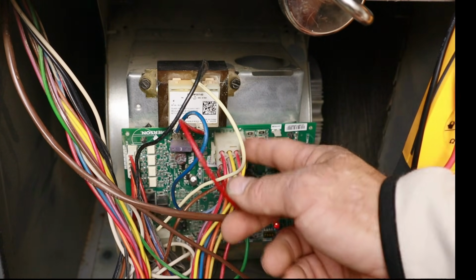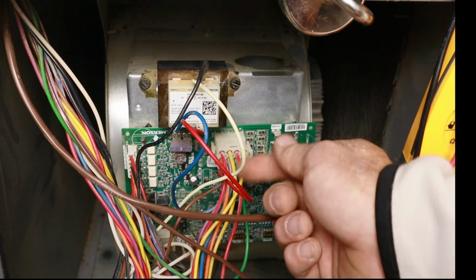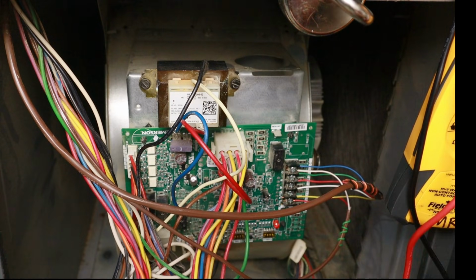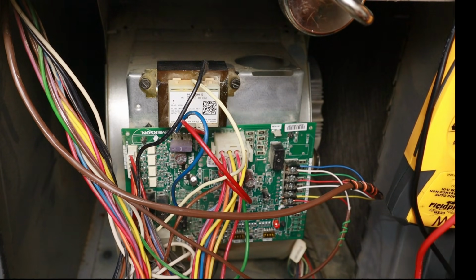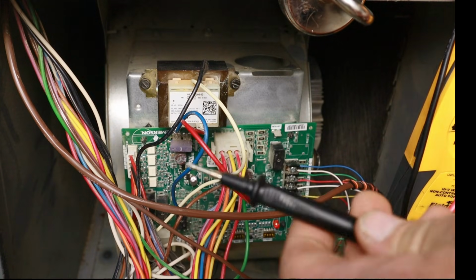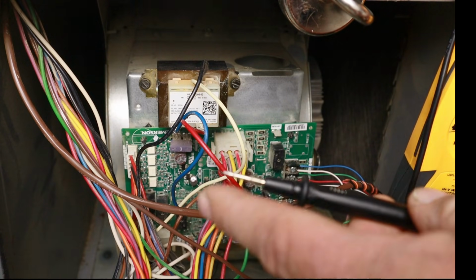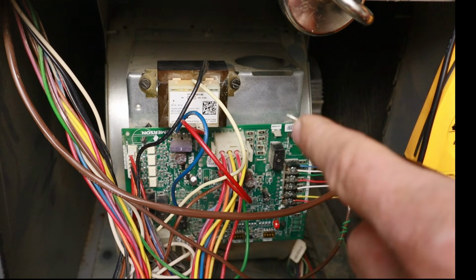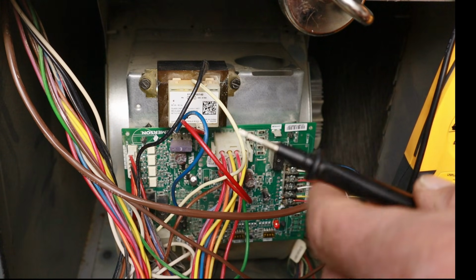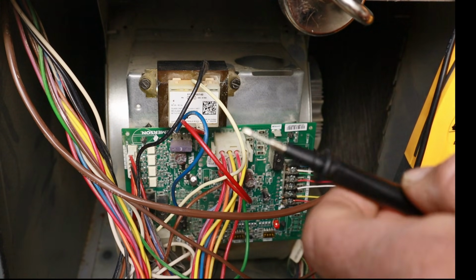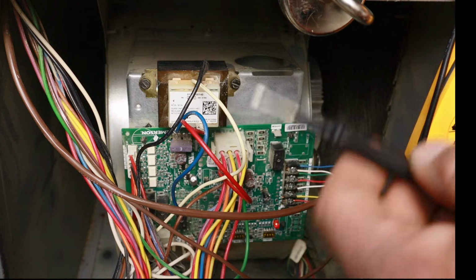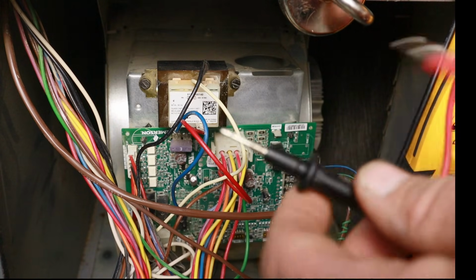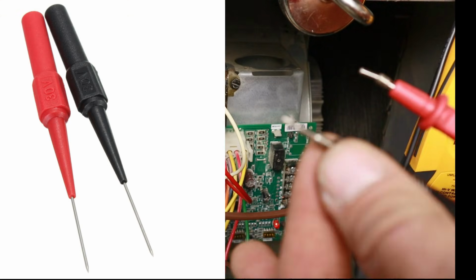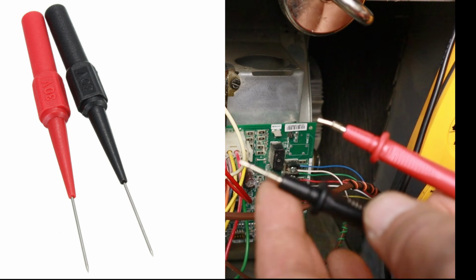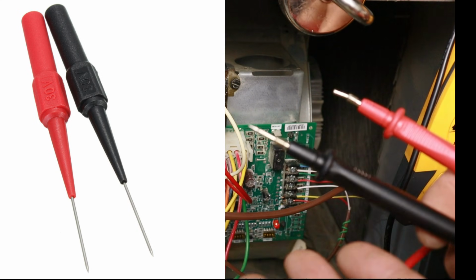Now when you take this Molex plug off, you can test from the other end, but you do not want to use your normal terminals on your multimeter, because this wide terminal will actually slightly damage the Molex plug connector, and you will not get a good connection, and that can cause all kinds of problems and the unit won't run properly. What you need are adapters that go on here that are very, very thin and fit in there, and that you won't have that problem.